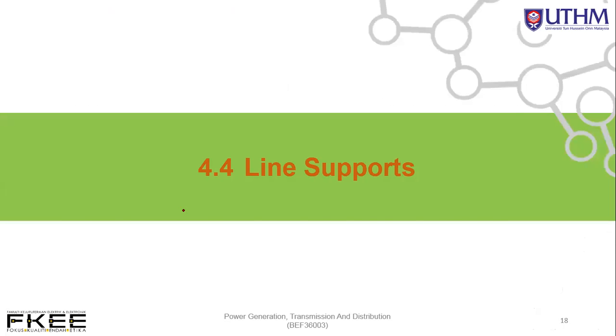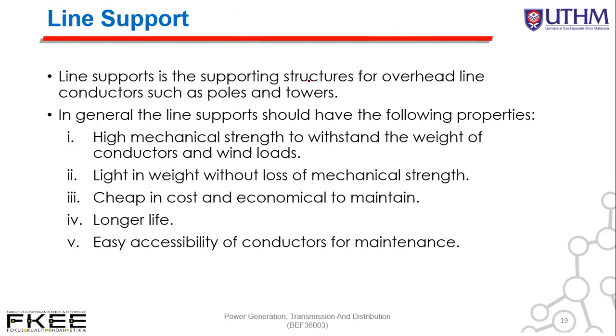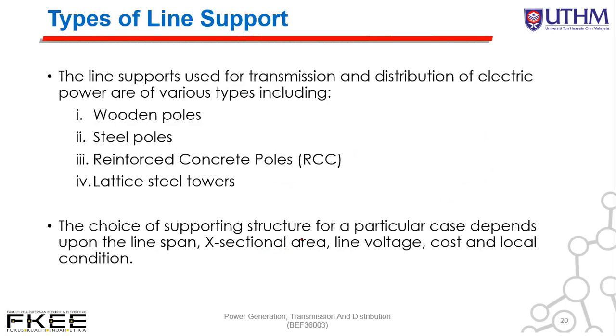Now let's see the line support. Line support is a supporting structure for overhead line conductors, such as poles and towers. In general, the line support should have the following properties. First, high mechanical strength to withstand the weight of the conductor and wind loads. Second, light in weight without loss of mechanical strength. Third, cheap in cost and economical to maintain. Fourth, longer life. And fifth, easy accessibility of the conductor for maintenance. There are four types of line support: wooden pole, steel pole, reinforced concrete pole, and lattice steel tower.